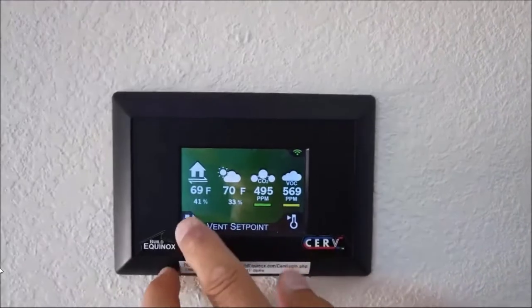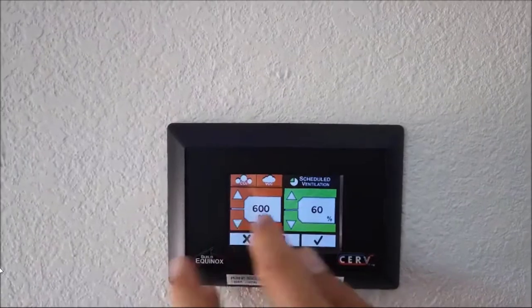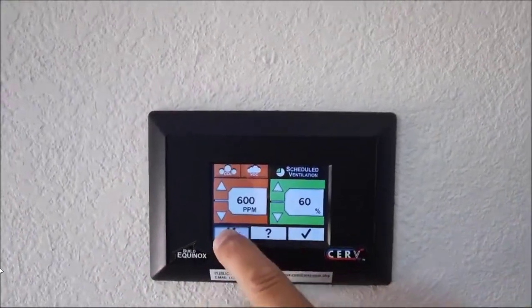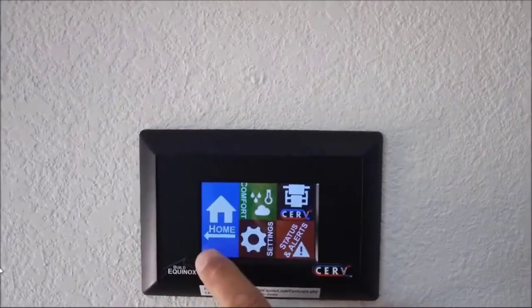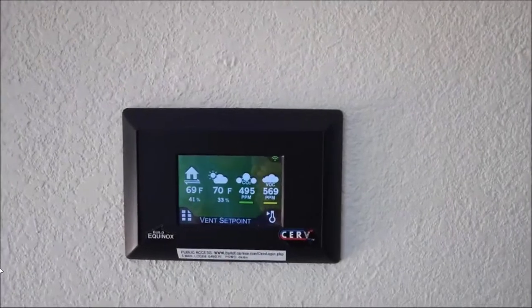I can set this for any CO2 level I want and recycle accordingly. I don't want the CO2 level to be higher than 600 parts per million. The ambient air is about 400. However, Stanford University studies the human brain and we start to slow down on our decision levels at 1,000 parts per million. In a conference room without fresh air but with cold air conditioning recycling, the CO2 level might be up to 5,000 — you may be falling asleep at a presentation.